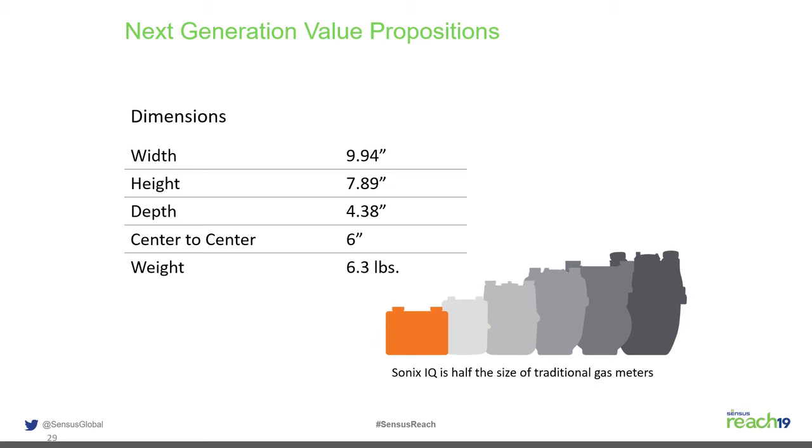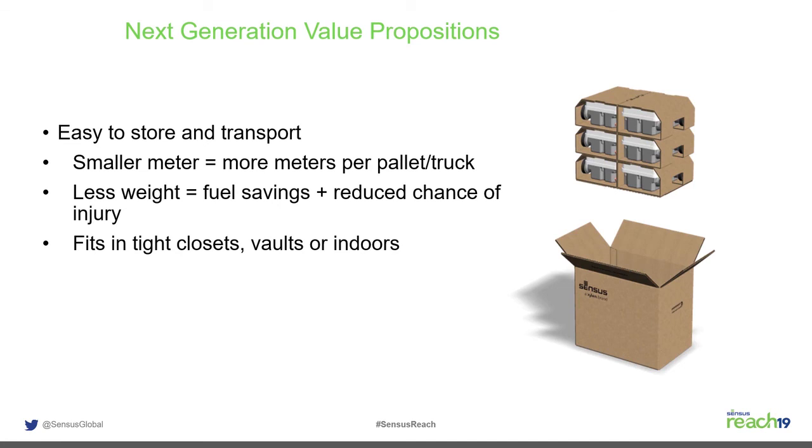The Sonix IQ is very small and weighs 6.3 pounds, which benefits handling and logistics. Nearly 6,000 Sonix IQ meters can be loaded on a trailer, compared to only 2,000 to 2,500 R275 mechanical diaphragm meters. The limiting factor is weight — approximately 43,000 pounds per trailer — not volume, meaning you get almost three times as many meters per shipment. The preferred installation orientation is connections up, though other orientations are acceptable in non-weather environments.